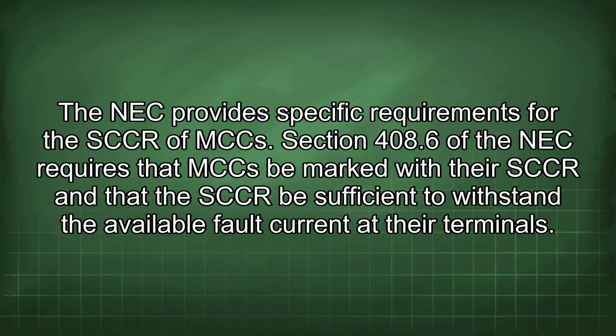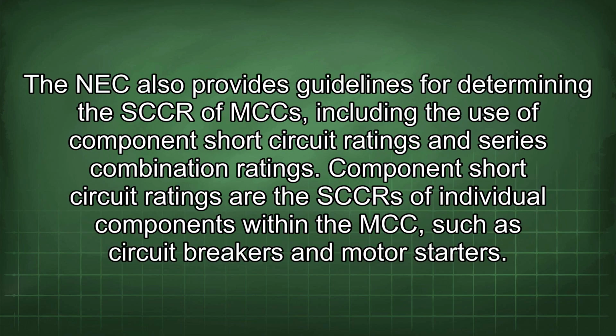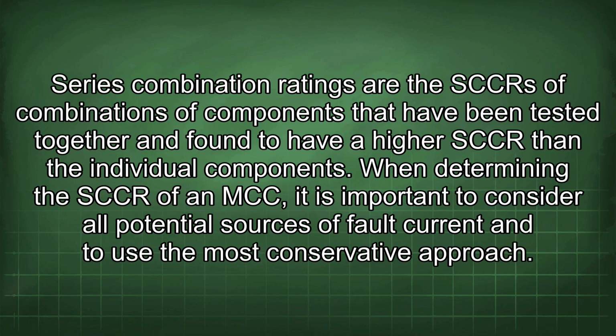Section 408.6 of the NEC requires that MCC be marked with their SCCR and that the SCCR be sufficient to withstand the available fault current at the terminals. The NEC also provides guidelines for determining the SCCR of MCC, including the use of component short-circuit ratings and series combination ratings. Component short-circuit ratings are the SCCRs of individual components within the MCC, such as circuit breakers and motor starters. Series combination ratings are the SCCRs of combinations of components that have been tested together and found to have a higher SCCR than the individual components.